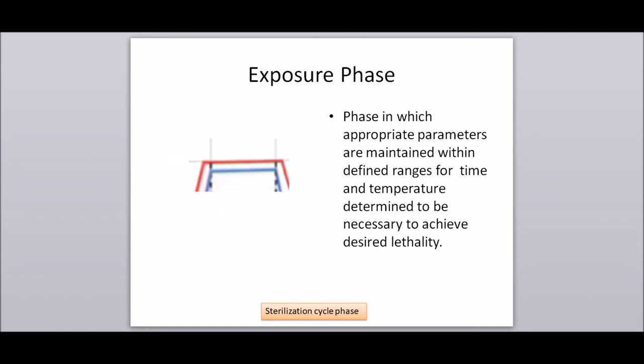Exposure phase: the phase in a sterilization cycle in which appropriate parameters are maintained within a defined range of time — i.e., exposure time or dwell time — and temperature determined to be necessary to achieve the desired lethality.